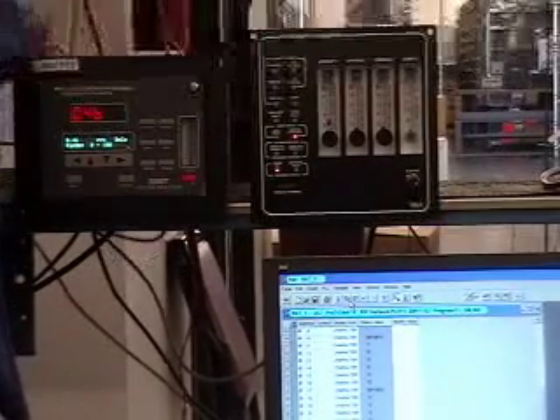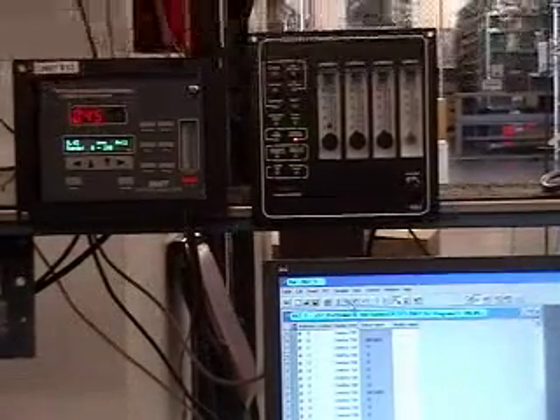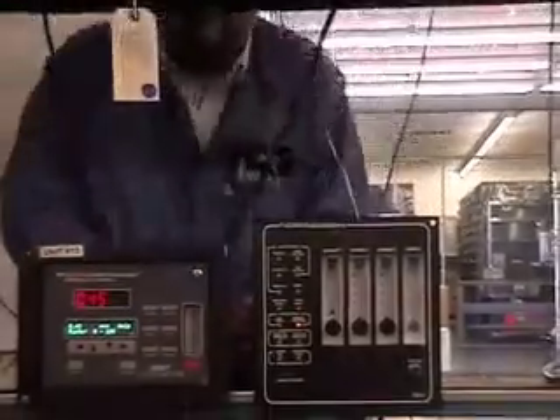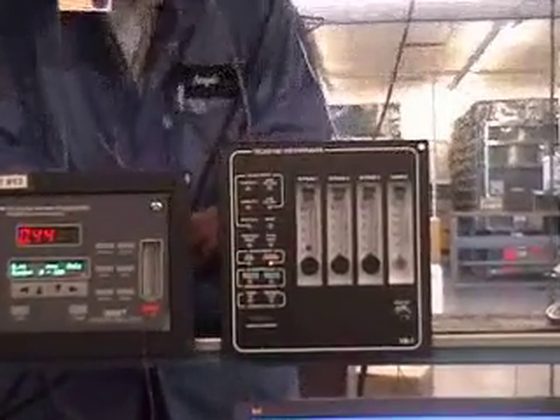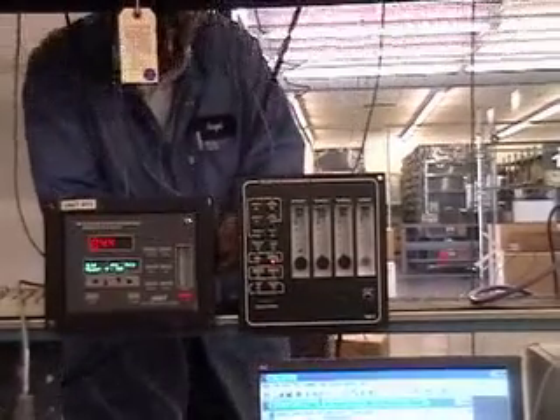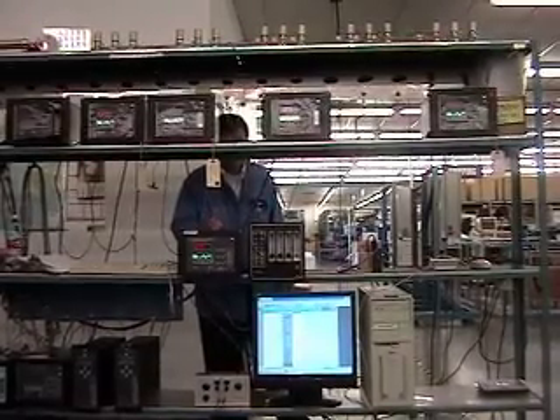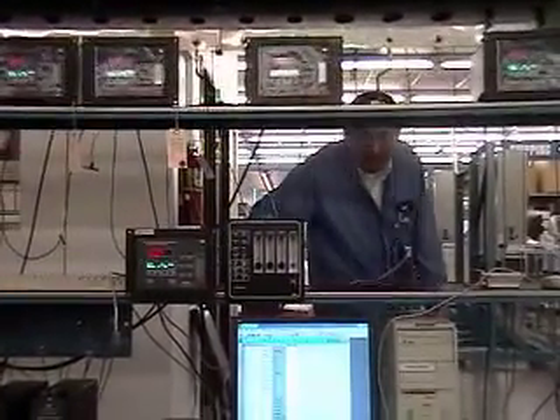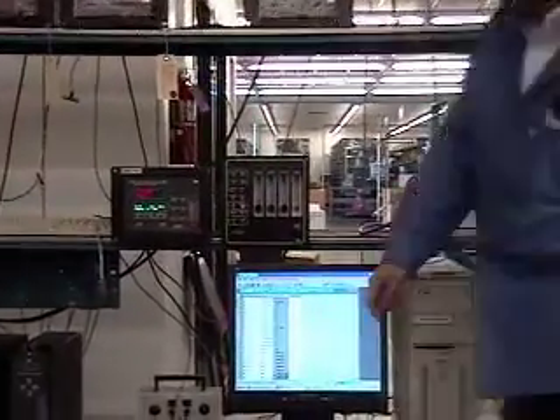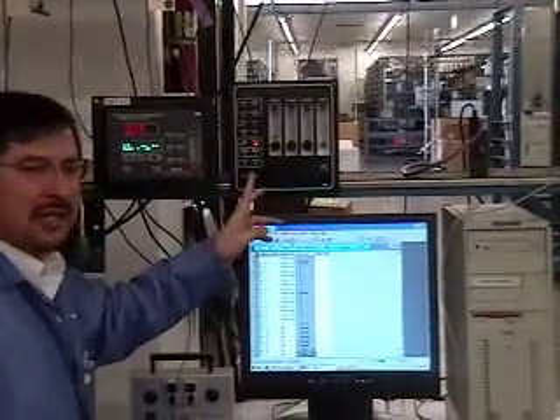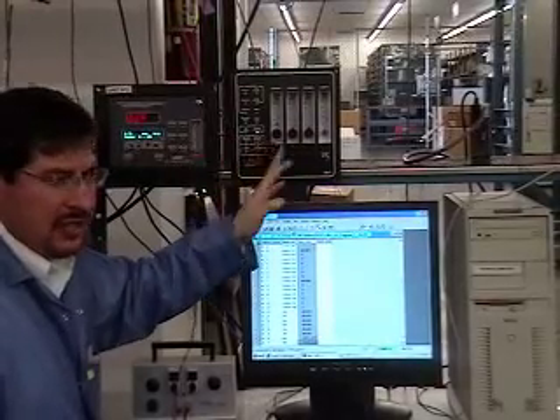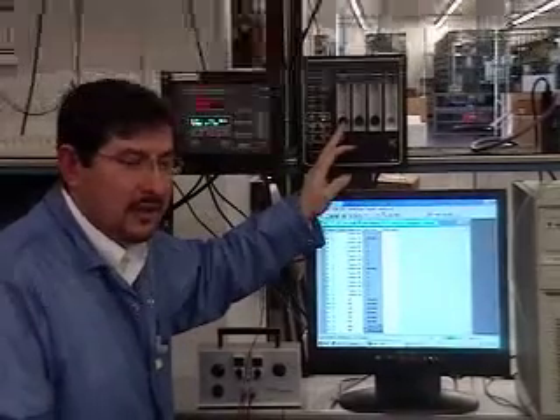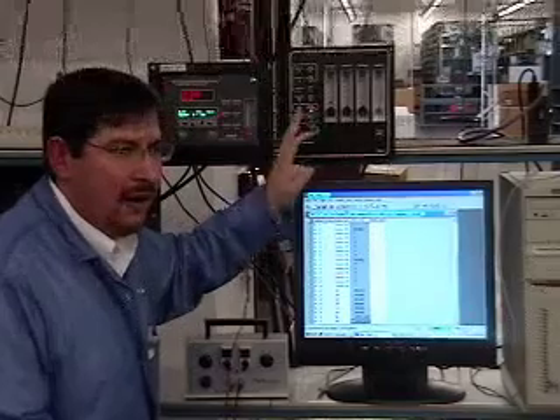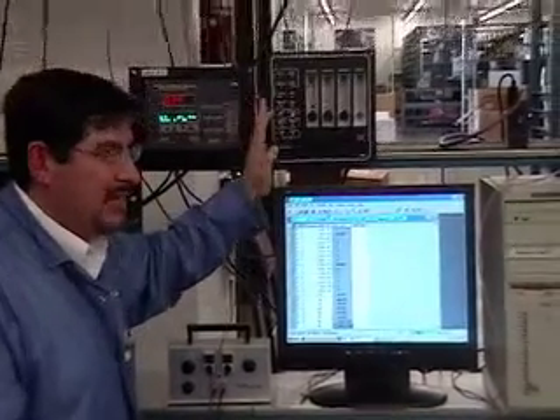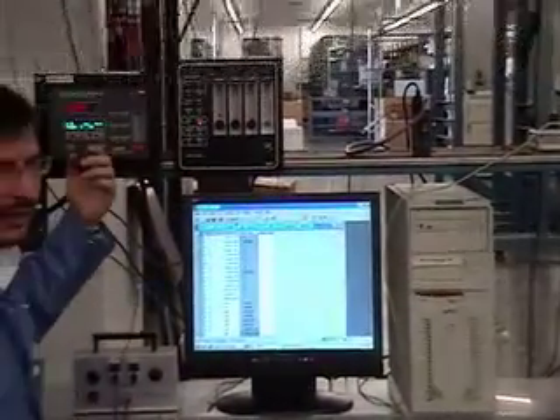But what I'm going to do, I'm going to disconnect the RS-232. I'm going to go to the back. And I'm going to connect the 4 to 20 milliamp to the BB1 and the 4 to 20 milliamp to the analyzer. Connected the RS-232 from the analyzer and connected a 4 to 20 milliamps output from the 3000 TA all the way to the BB1, to the analog input on the BB1. So now what will happen is when I move the manual override switch down, the BB1 first checks if there is anything over 4 milliamps in the analog input. If there is, then from now on it will be in half digital mode, which means it has digital connection to the Step 7 PLC, but it has no digital connection to the 3000 TA analyzer.